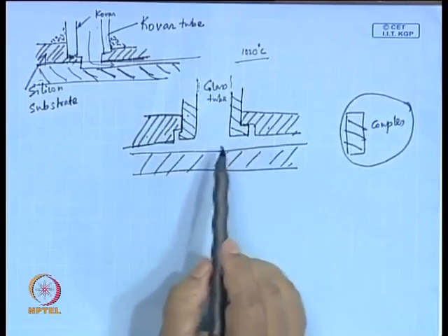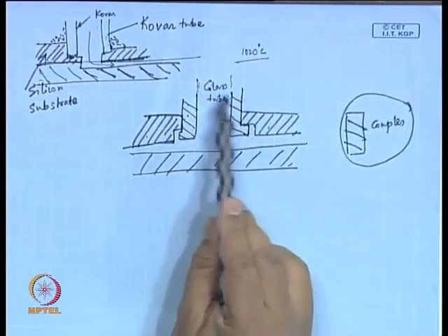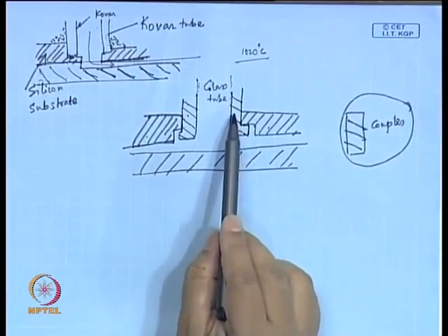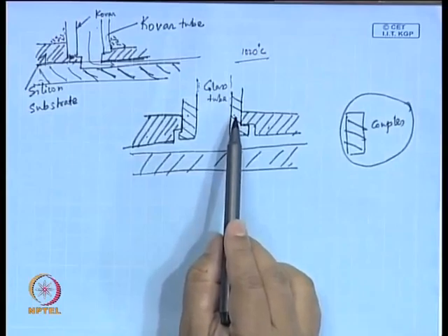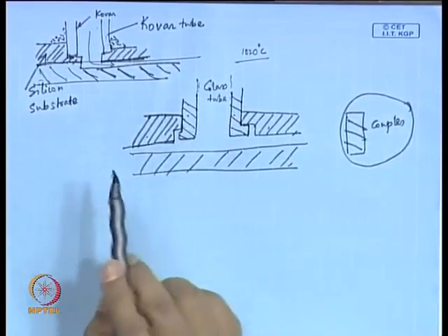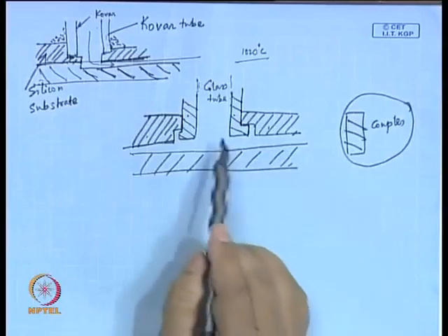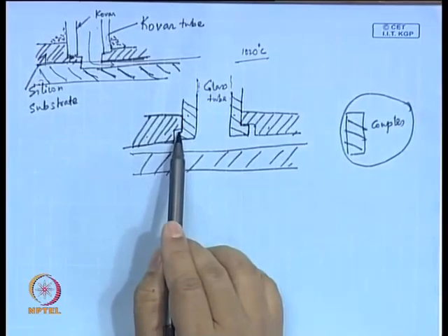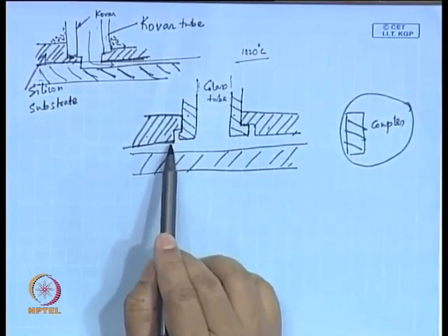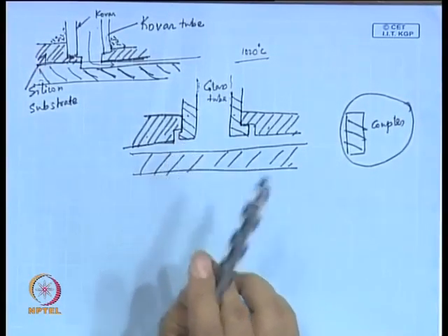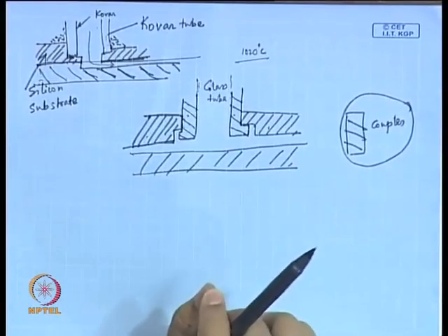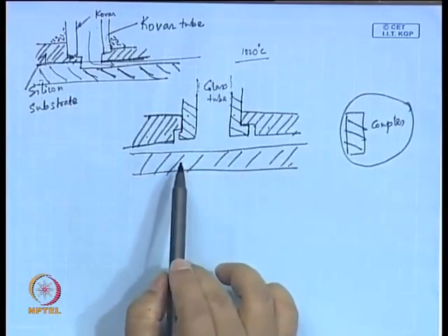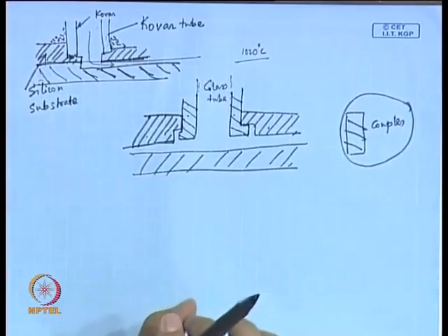Now, the idea here is that you apply some heat to this coupler material. This coupler material is made of plastic. This plastic material melts, may not be perfectly melt and leaking from everywhere, it just gets softened, it melts to some extent, and this plastic material flows. When it flows through various gaps, the places where the leakage can take place, it will flow through those places and it will make a permanent sealing.